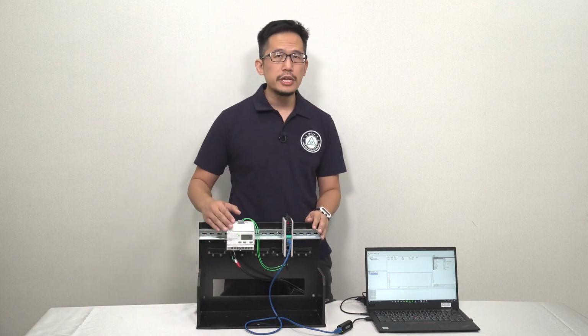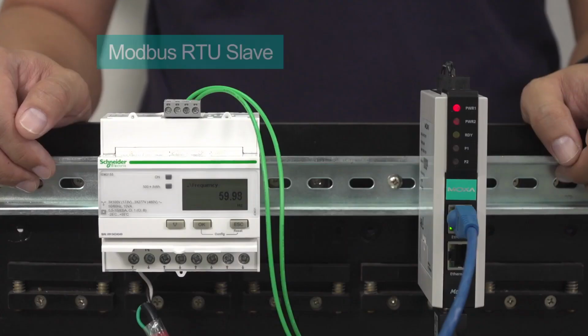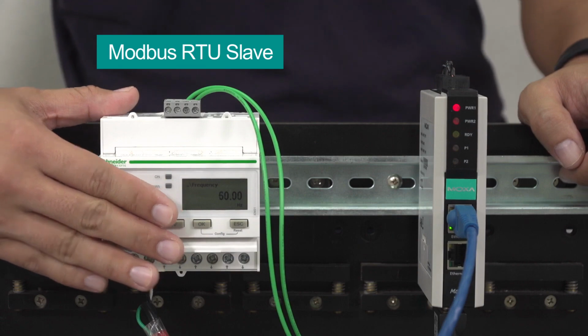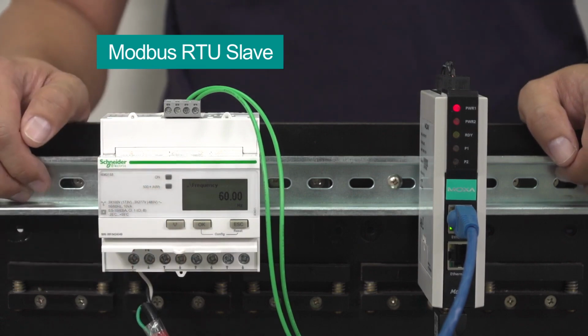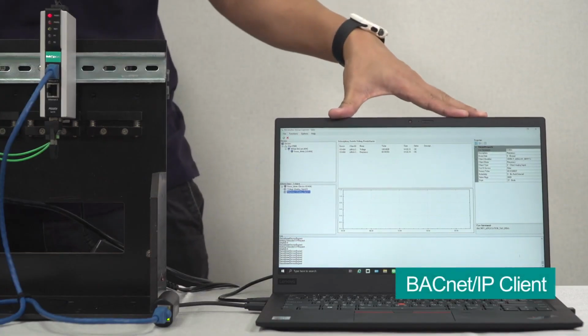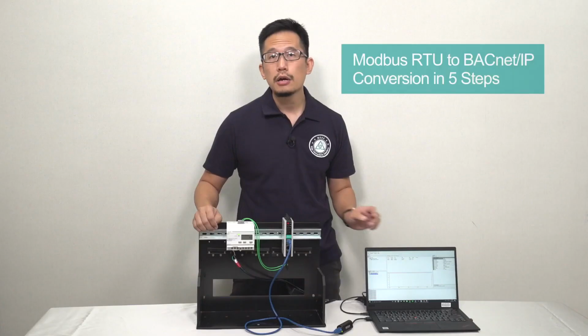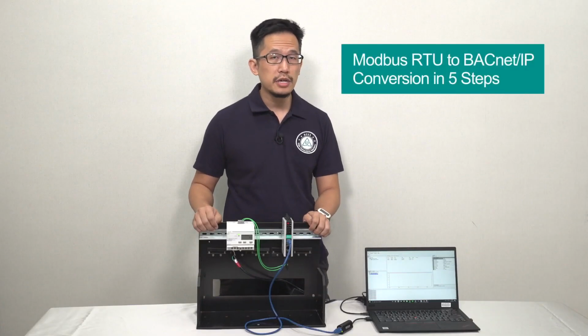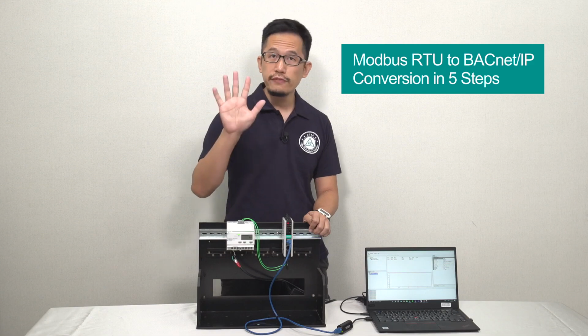To connect this power meter to our BACnet IP network, we have to convert Modbus RTU protocol, which the power meter uses, to BACnet IP protocol, which our BACnet IP client uses. I'm going to show you how to set this up with the MGate 5217 in just 5 steps.